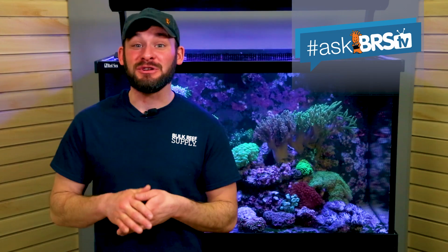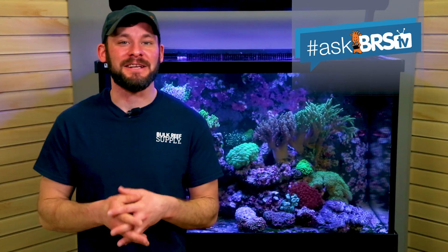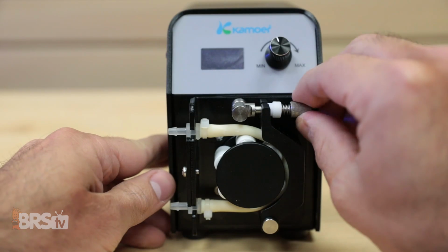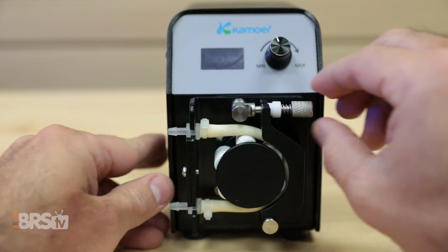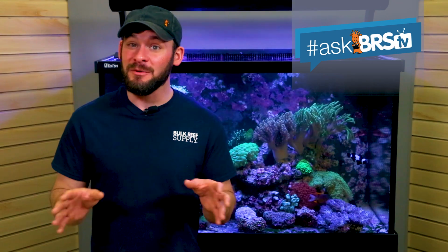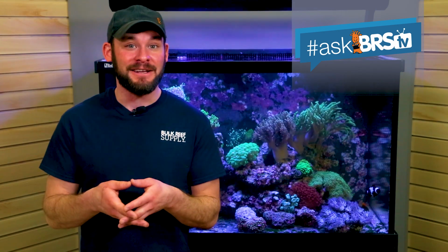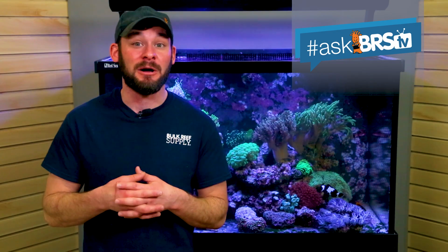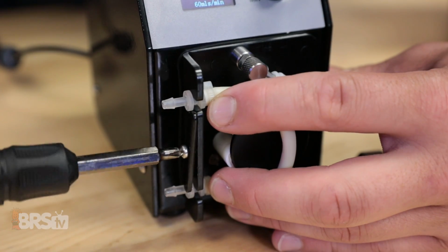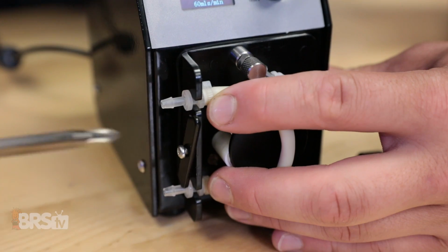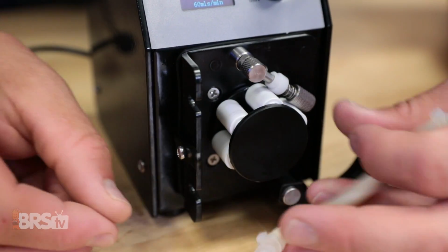One note here, if you turn your pump back onto its normal operating speed and the head just won't turn, you may need to loosen the tensioner just a little bit to free the rollers. Along with that, although you can remove the bracket screw that holds the tubing ends on the pump completely, you don't really need to, and you'll definitely save more time by just loosening it enough to free the tubing.